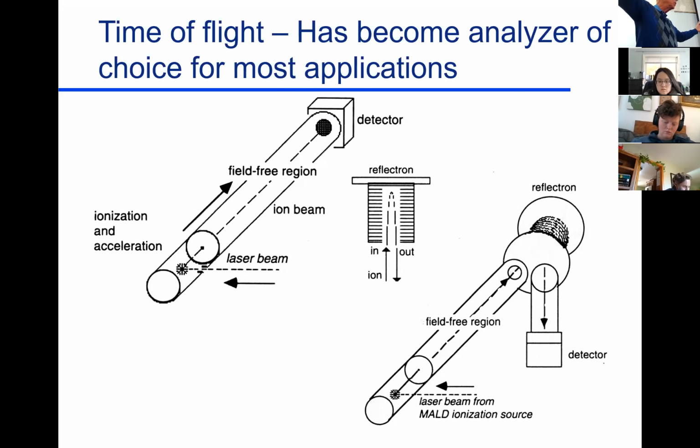So I've got a tube that's maybe that long. I bombard the sample for a fraction of a second, and then draw the ions out. Now there's kind of a race going down the tube. The smallest ones get to the detector first, and I measure them. Then the bigger ones, and bigger and bigger, and you do it all over again. The ability to monitor nanoseconds permits this to be really accurate. So it's a simple detector, and now, like I say, the workhorse in the industry.